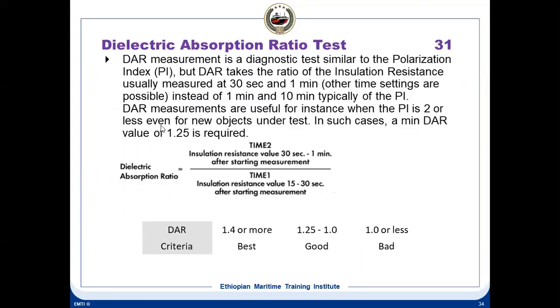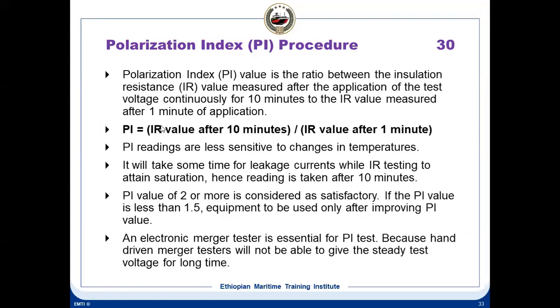So here, for insulation testing, as I told you, one is the IR test, one is the polarization index test. The IR test is for 1 minute. You have to apply the Megger for 1 minute in the case of the IR test. In the case of the polarization index test, you have to apply it for 10 minutes, and also the 1 minute reading. The 10 minute reading you get is divided by the 1 minute reading. That value has no unit. You will get like 1.5, 2, 3, 4. This has to be more than 2.